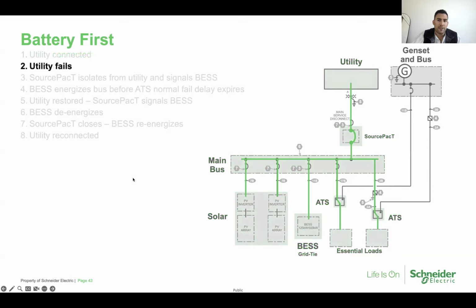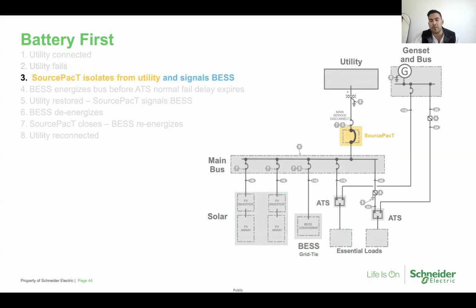In this scenario, when utility fails, the entire system goes dark. Again, those inverters shut down inherently. That's per code. They're designed to shut down to prevent any backfeed. Once they shut down, SourcePacT will detect the outage. Again, this outage time, or the moment that breaker opens, can be set from 0 to 6 seconds. In this scenario, you want to probably call on that battery energy storage system first. You can program that to 1 second or 0 seconds, where as soon as you lose power, that SourcePacT device opens and sends a signal to the battery energy storage system telling it, hey, we lost power. Change state from grid interactive to grid forming mode.